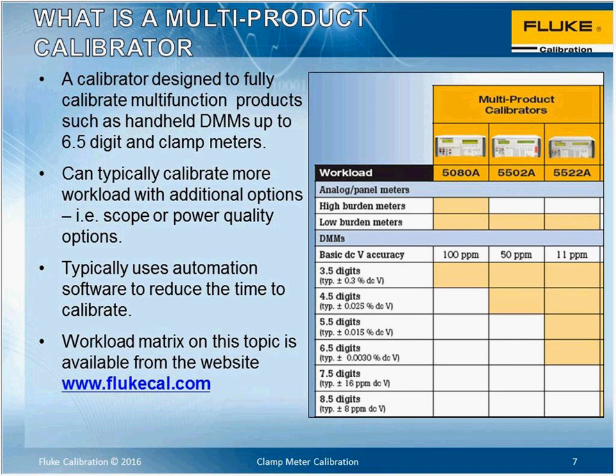Typically they use automation software to reduce the time to calibrate, and we'll discuss this a bit more. You have many options today on the market for calibration software. Fluke offers MetCal and MetTeam, which allow you to load a procedure for a product, like a handheld, and it'll run through the calibration sequence, giving you guidance like 'change range now.' It really does speed up the calibration process, so if you're doing high volumes, it makes sense to have that functionality with your multi-product calibrator.